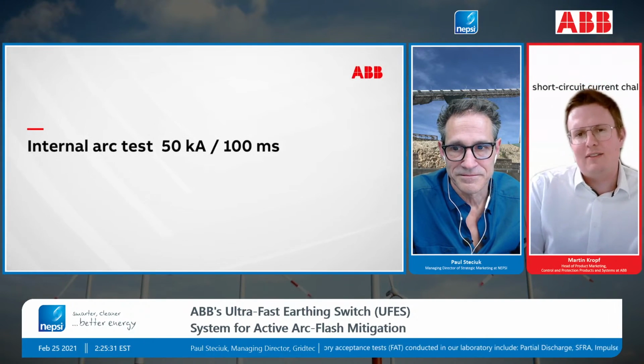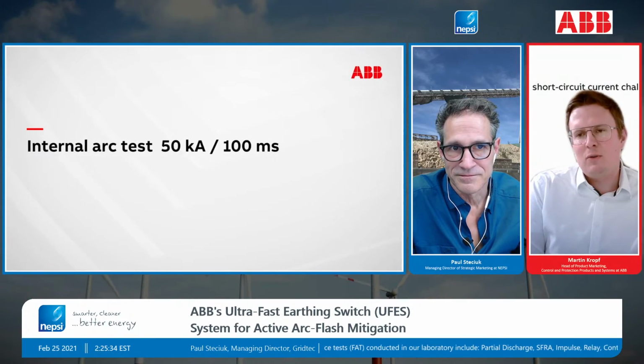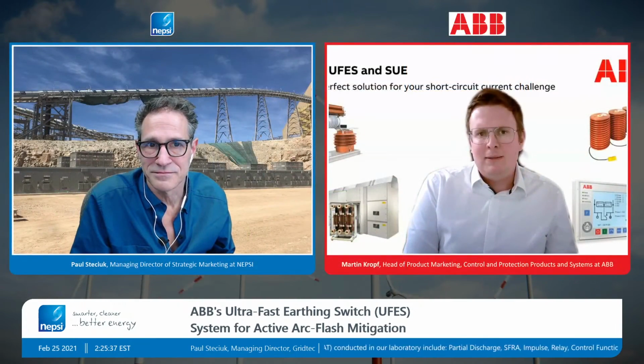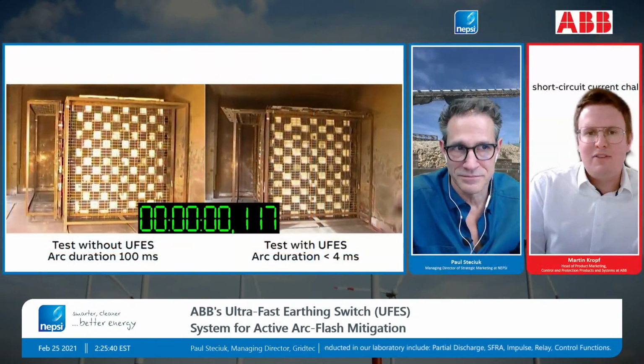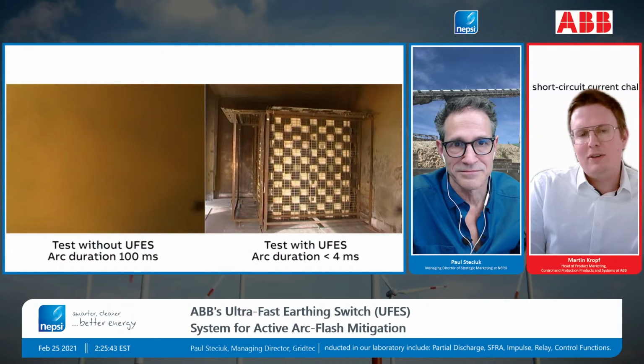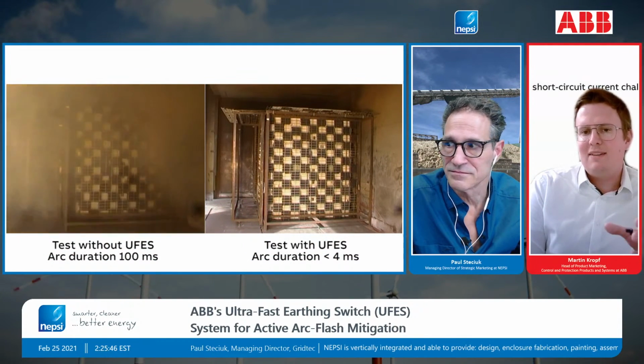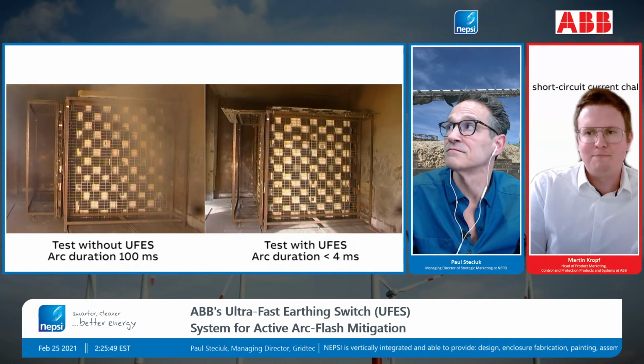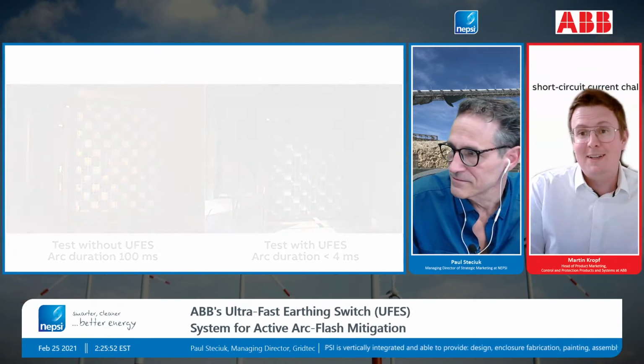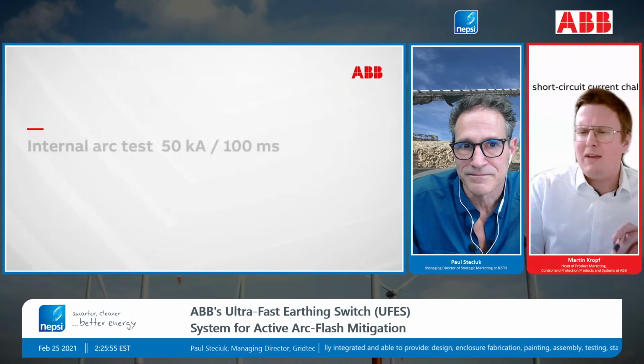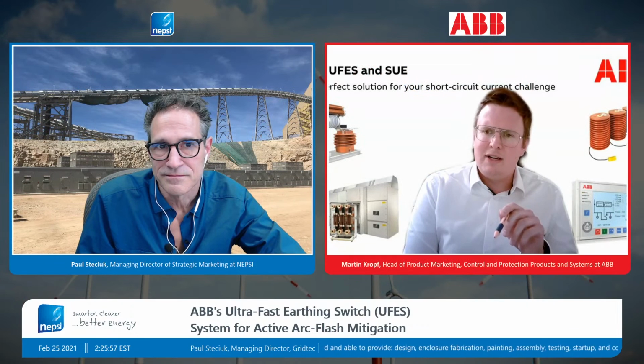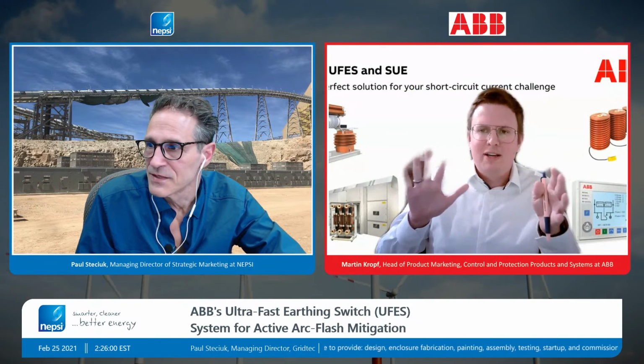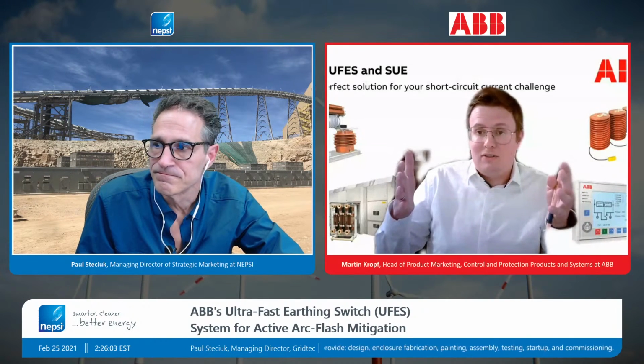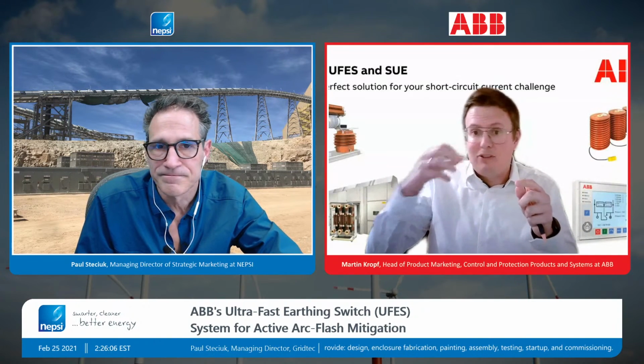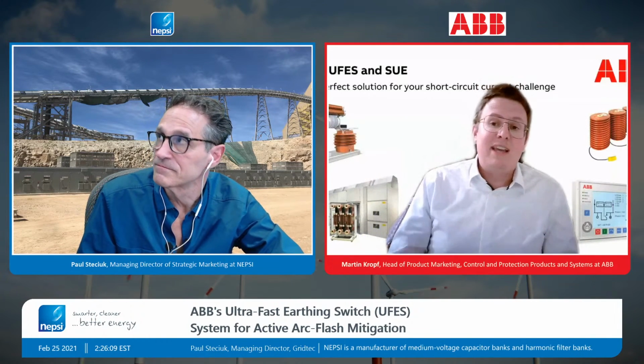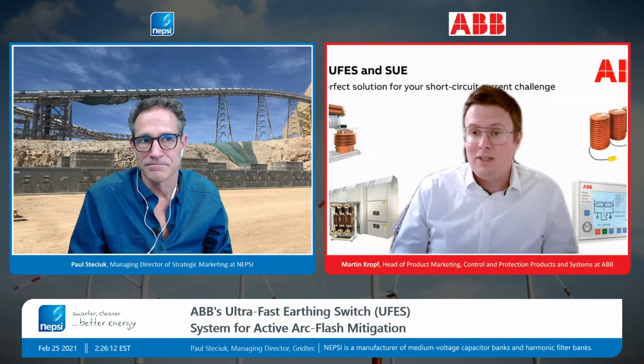We're going now for an internal arc test, and this is 50 kA, which is quite at the upper level. Now the video is gone, but it's 50 kA. On the left hand side, 100 milliseconds, on the right hand side, 4 milliseconds. The 4 milliseconds is very boring. What you have seen as well are these indicators around the switchgear, which is standard procedure in internal arc tests. These indicators are not allowed to catch fire, and that's why they are there. If they catch fire, the test is not passed.